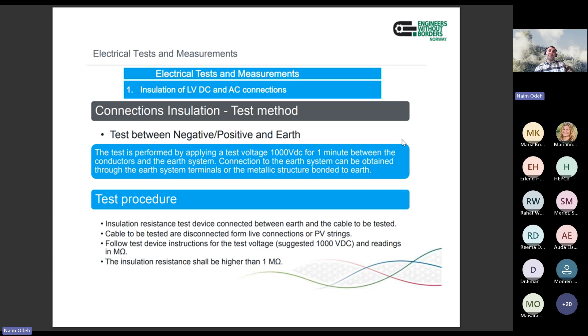I know the DC voltage will be high most of the time, but as you know, for solar it is not a continuous high voltage, it keeps changing all day. So there is a big difference between having a continuous 1000 volt DC connected all the time and having a variance in the voltage. This is why it is not recommended to keep repeating this. The best thing is to have a way of marking the strings that you test or inspect, then move on to the next. And don't forget to keep the MC4 connectors closed after you finish, either by using tape, or some MC4 connectors come with small lockers where you can close them to keep them away from dust, water, and others.